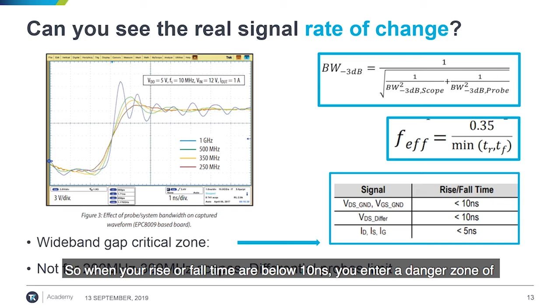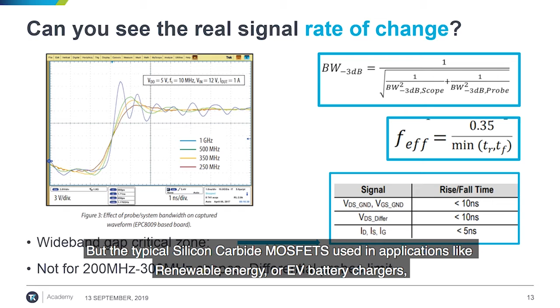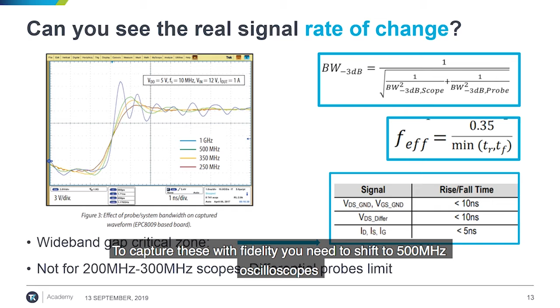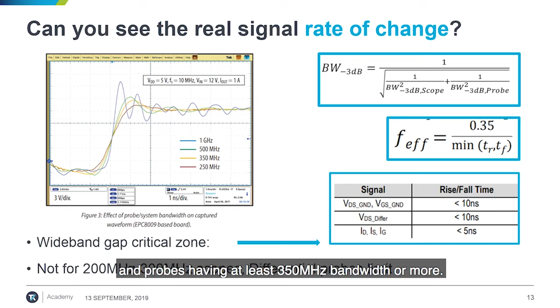So Tektronix, the new electrical differential probes, have 200 megahertz of bandwidth, and if you match them with a 200 megahertz oscilloscope, the rise and fall time you can capture cannot be less than 9 or 10 nanoseconds. But the typical silicon carbide MOSFETs used in applications like renewable energy, EV (electric vehicle) battery chargers, DC-DC converters and power supplies, also up to 1 kilovolt, the VDS rise and fall time may range generally between 4 to 8 nanoseconds. So to capture this with fidelity, you need to shift to 500 MHz oscilloscopes and probes having at least 350 MHz bandwidth or more.